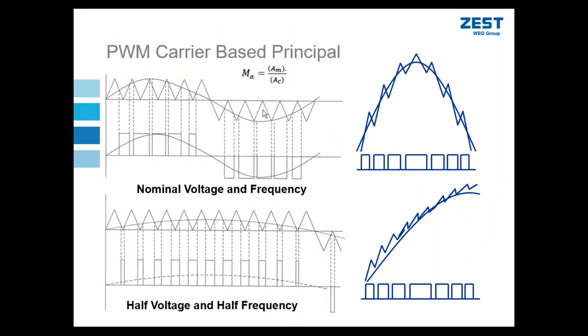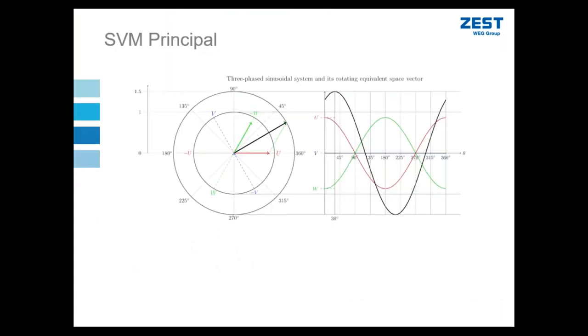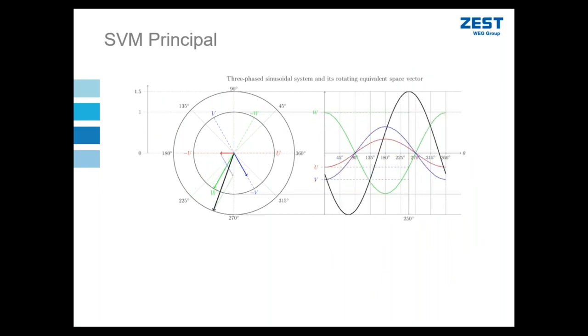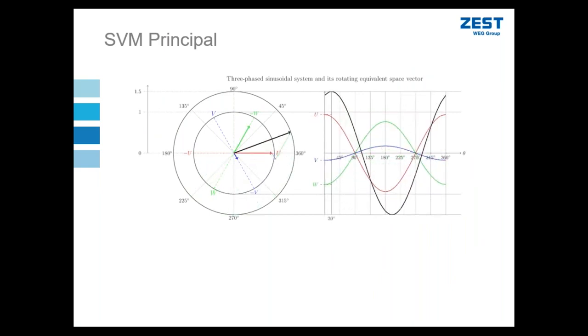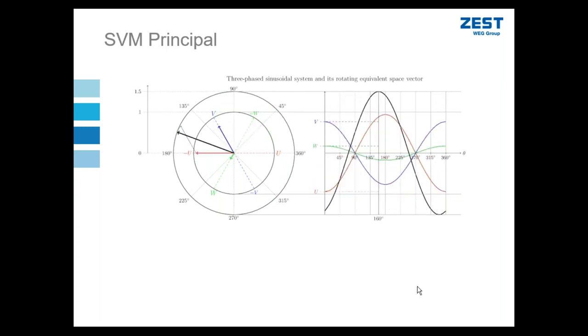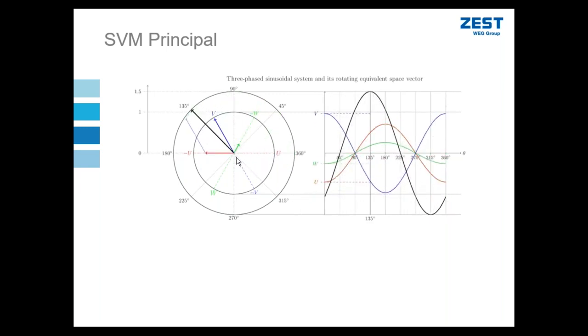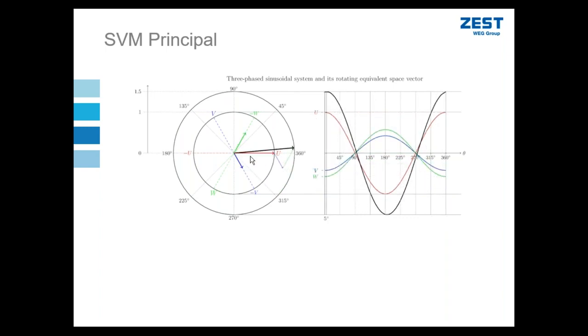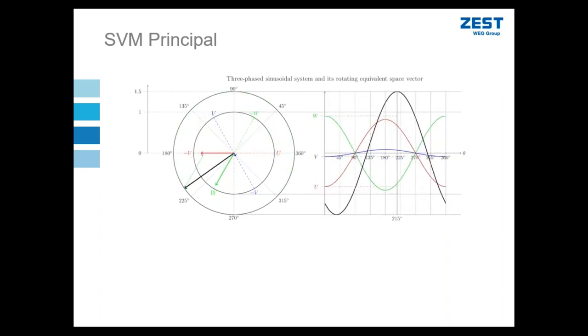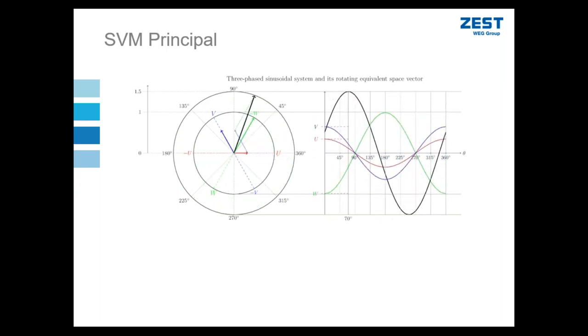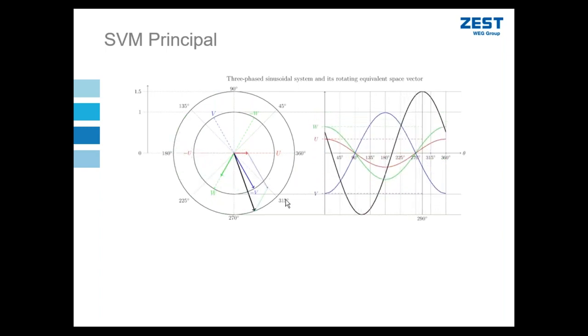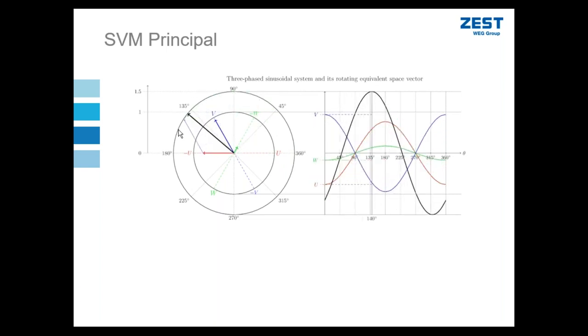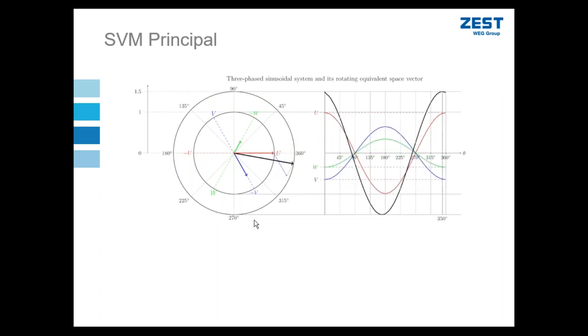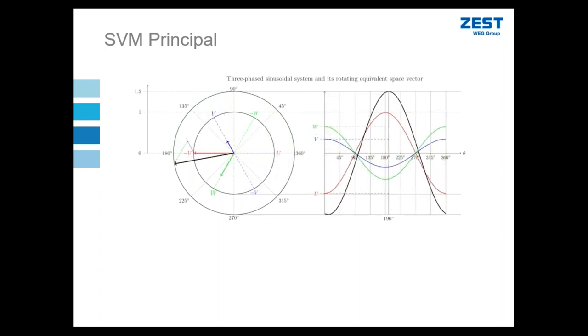All right, so this carrier-based frequency and reference sinusoidal signal is an old, outdated way to do output switching control of a VSD. There are much more modern techniques, for example, space vector modulation. So we will very briefly describe how space vector modulation works. If you consider a normal three-phase sinusoidal supply to a motor, we can break that up into three vectors, our three phases, ABC or UVW. And we can do a vector sum of those three vectors at any given time in space and create one single rotating vector to represent the motor three-phase voltage condition at any given time.